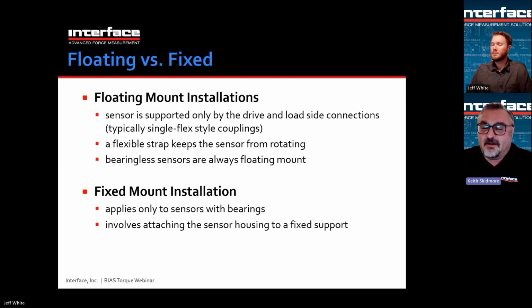So the sensing element assembly must be supported by its end connections, which means it floats in the middle. And that would be, say, between a motor and another motor, a transmission, or a motor and a brake. Fixed mount only applies to sensors with bearings because it talks about a housing holding the shaft, and then that housing mounting to, say, a plate. When used in such a way, it's just really for alignment and support of the shaft. It's not at all intended to be used as a bearing block or a jack shaft or anything. Because again, the bearings in a torque sensor are not a consumable item that is readily replaced. So you don't want to use the torque sensor as a bearing block and wear out the bearings. We'll show some examples in the coming slides.